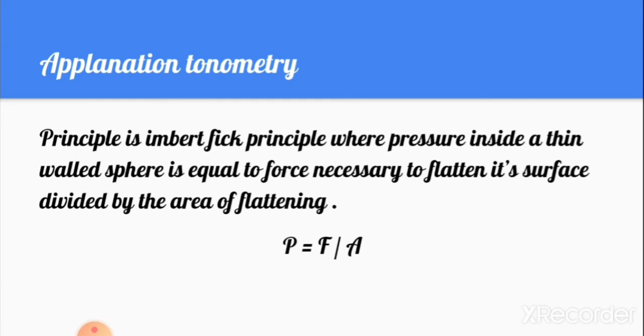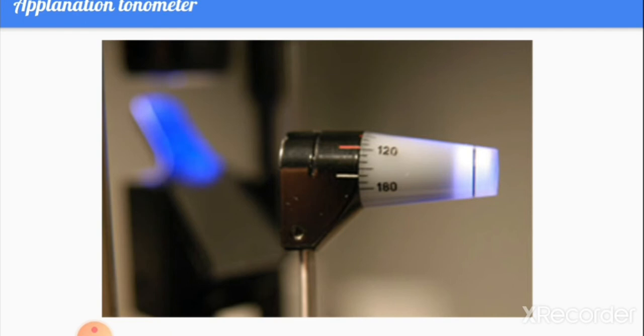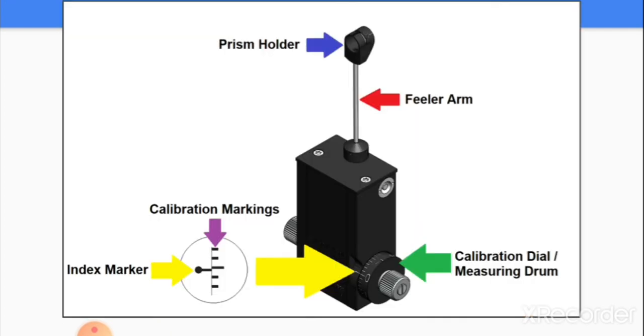Applanation tonometry is based on the Imbert-Fick principle, which states that the pressure inside a thin-walled sphere is equal to the force necessary to flatten its surface divided by the area of flattening. Here, P stands for pressure, F for force, and A for the area the probe is covering.